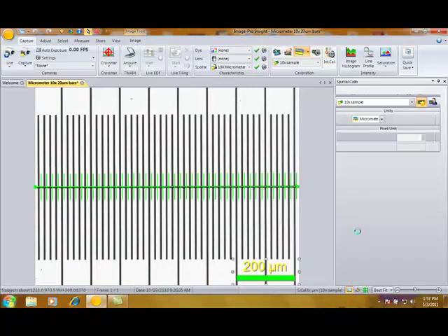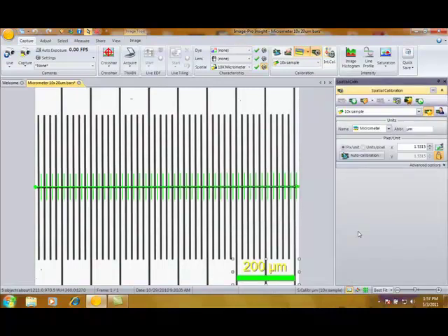So the auto-calibrate routine will automatically go through, find all the lines on the image, and then display an overlay to show that it's complete. In this case, it's showing me the name, microns, and also reports, in this case, pixels per unit, where I could choose units per pixel. So now I'm complete, the whole process is finished, and I'm ready to go on to do another objective or whatever else may be appropriate.